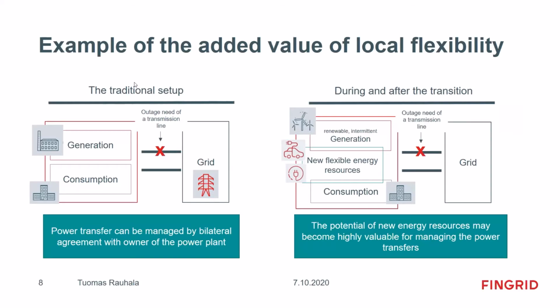In the traditional setup, shown on the left side of the screen, there's a region with some generation and consumption. There are two tie lines, transmission lines, connecting the region to the grid. For some reason, for example maintenance or refurbishment of a line, we need to take it out of service. Traditionally, we've been able to manage the transfer, keeping the remaining line within its rated capacity, by making a separate commercial agreement with the owner of a generation plant, so they would regulate their power so that transmission on the remaining line would not violate the line's capability to transmit current and power.